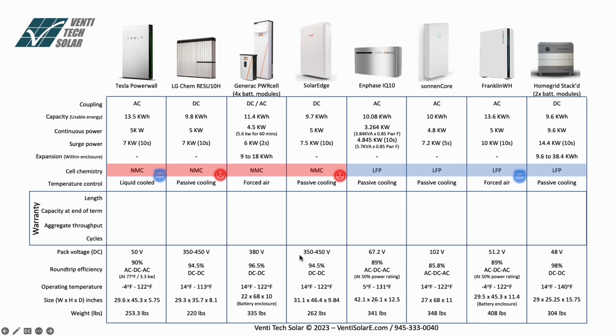And most of these also had to have a converter from DC to DC, from low voltage DC to high voltage DC, to be able to match the inverter, just like the SolarEdge also had to do the same. I think internally the pack is 50 volts or 56 volts, something like that. Enphase works at 67 volts, SonnenCore 202 volts, 102 volts. The Franklin uses 51.2 volts, and 48 volts for the home grid stack.